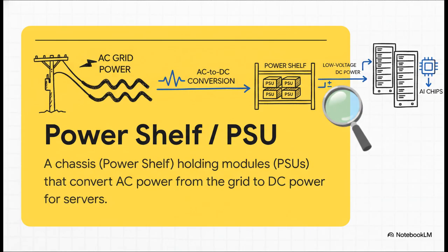You can think of it as a big chassis that's packed with power supply units, or PSUs. They're basically the souped-up power adapters for the entire system. They grab that high-voltage AC power coming from the grid and convert it into the stable, low-voltage DC power that those hungry AI chips actually need to run.